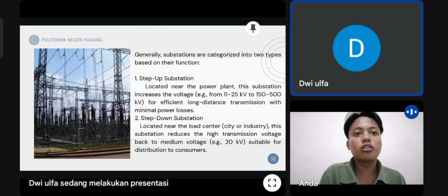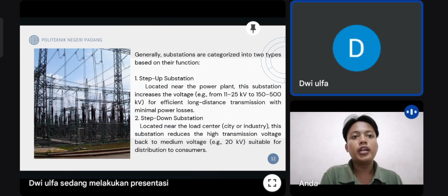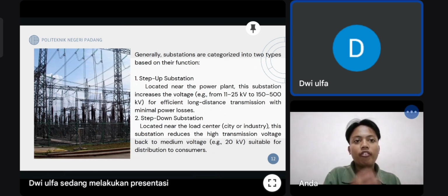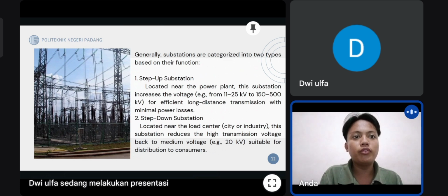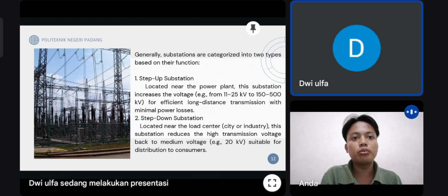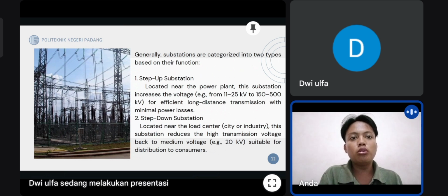Generally, substations are categorized into two types based on function. One, step-up substations, located near the power plant. This substation increases the voltage from 11 to 25 kilovolts to 115 to 500 kilovolts for efficient long-distance transmission with minimal power losses. And two, step-down substations, located near the load center. The substation reduces the high transmission voltage back to medium voltage, 20 kilovolts, for distribution to consumers.